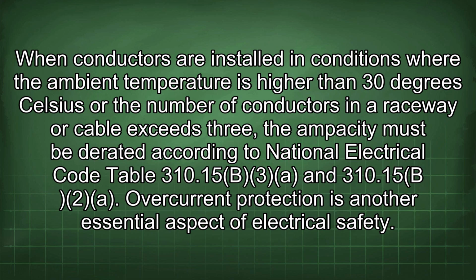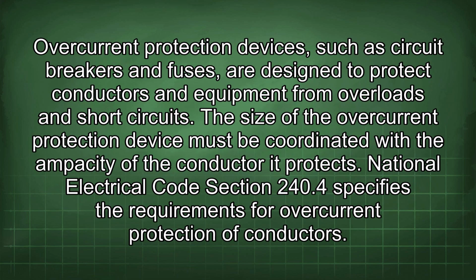When conductors are installed in conditions where the ambient temperature is higher than 30 degrees Celsius or the number of conductors in a raceway or cable exceeds 3, the ampacity must be derated according to National Electrical Code Table 310.15(B)(3) and 310.15(B)(2). Overcurrent protection is another essential aspect of electrical safety. Overcurrent protection devices, such as circuit breakers and fuses, are designed to protect conductors and equipment from overloads and short circuits. The size of the overcurrent protection device must be coordinated with the ampacity of the conductor it protects. National Electrical Code Section 240.4 specifies the requirements for overcurrent protection of conductors.